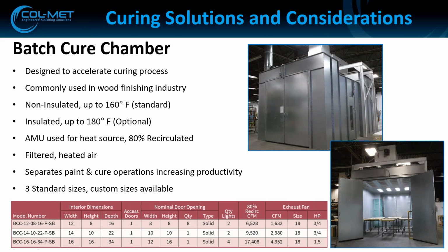The non-insulated can go up to 160 degrees discharge temperature, the insulated up to 180. Typically we see these running at 140 or lower - again, just trying to speed up the curing process. The heat source is an air makeup unit with 80% recirc, which helps save energy, and the air is filtered. Another benefit of a Batch Cure Chamber is that you can have a spray bake booth, but if you're baking, you're not spraying. So by having a standalone Batch Cure Chamber, you can increase productivity and process more parts.